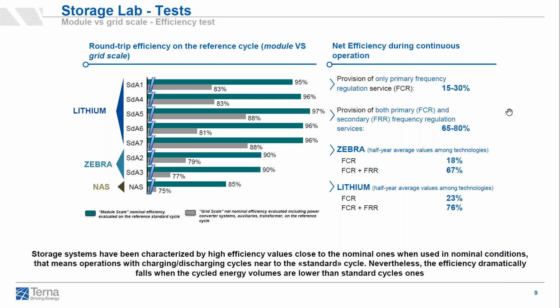On the right, we can see how the efficiency is impacted by the rate of utilization of the ESS. For example, in the case an ESS is operated just to provide the one service of primary frequency regulation, the efficiency is pretty low, between 15 and 30%. While if we add another service such as the secondary frequency regulation, the efficiency is higher and close to nominal value, between 65 and 80%. And this behavior is common also to Zebra technology.